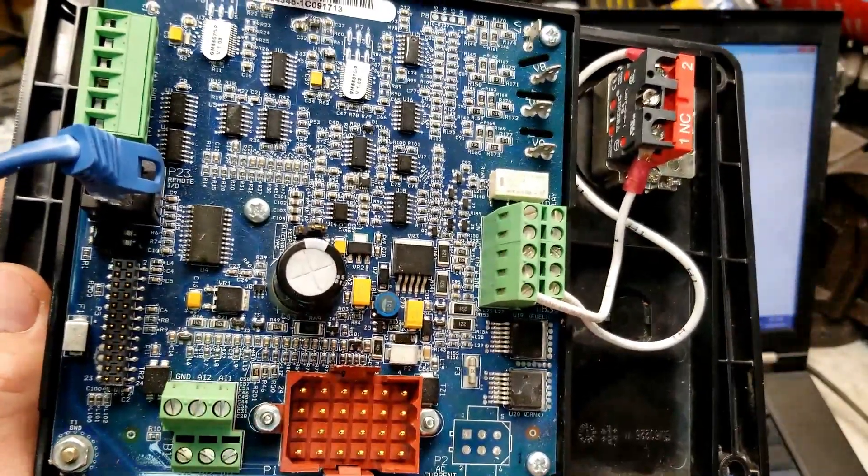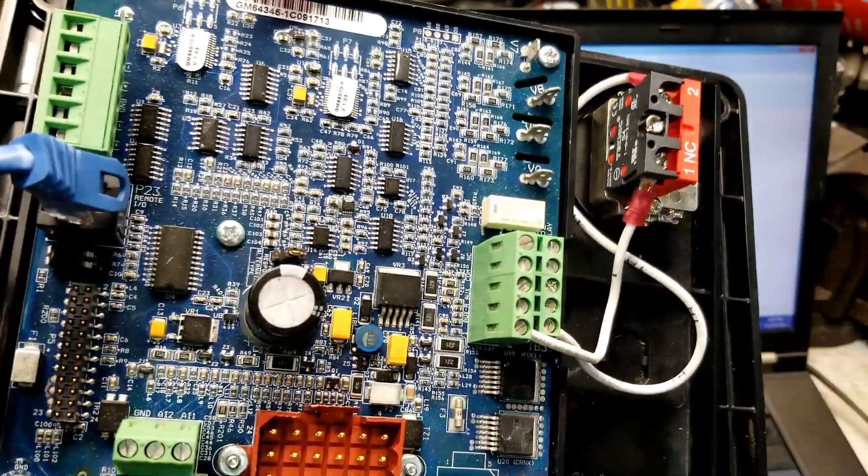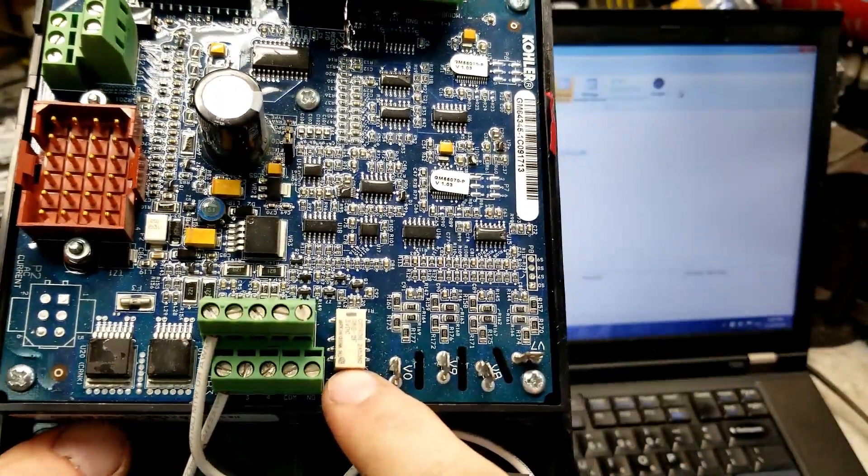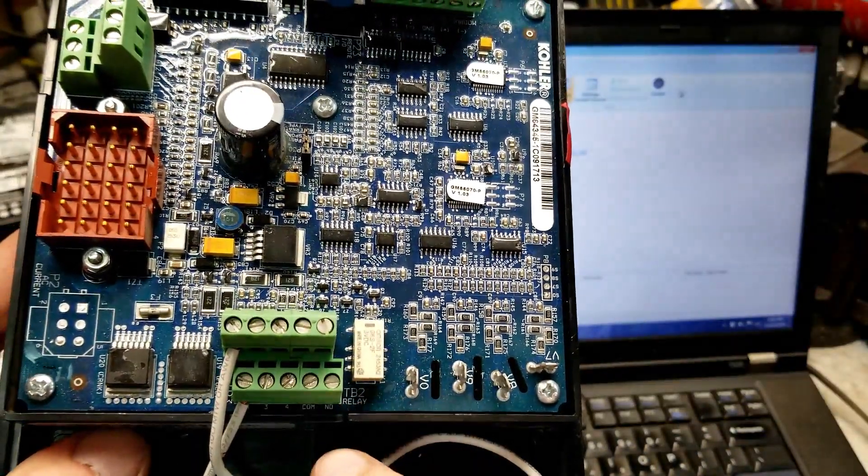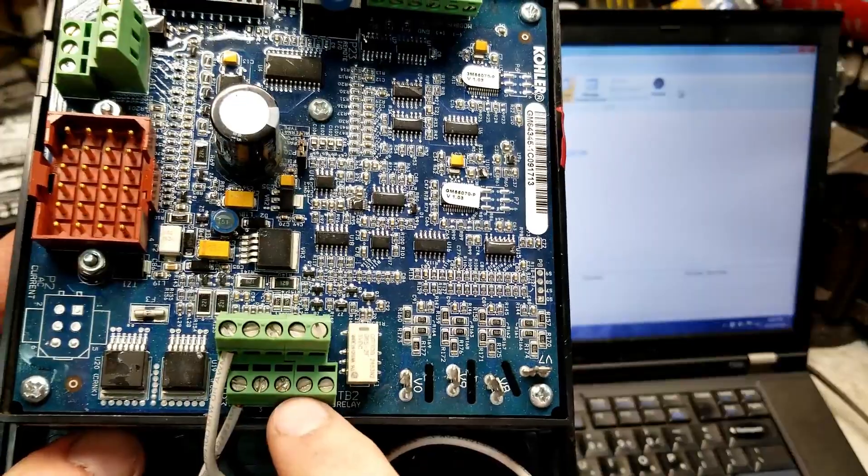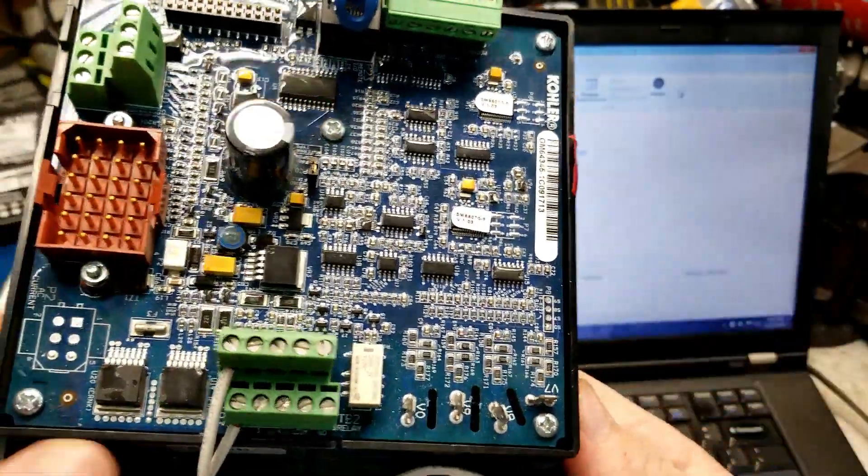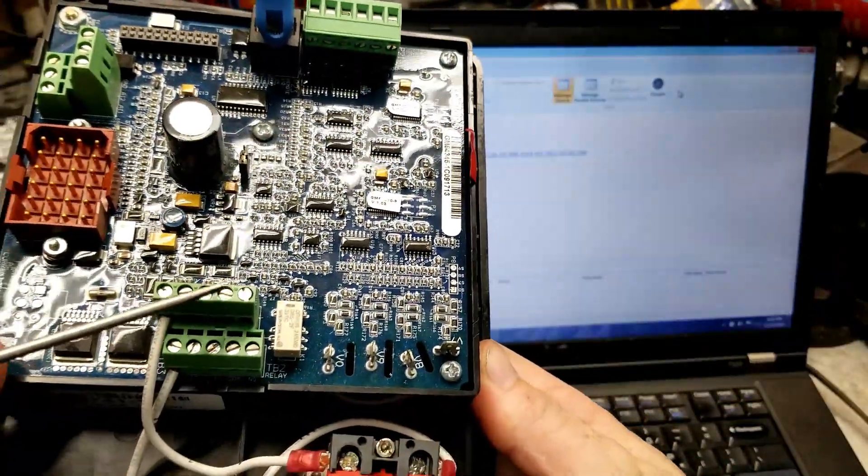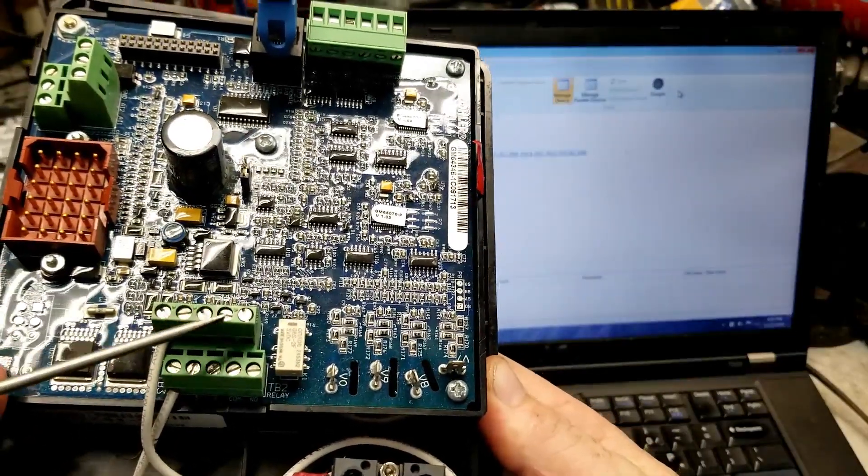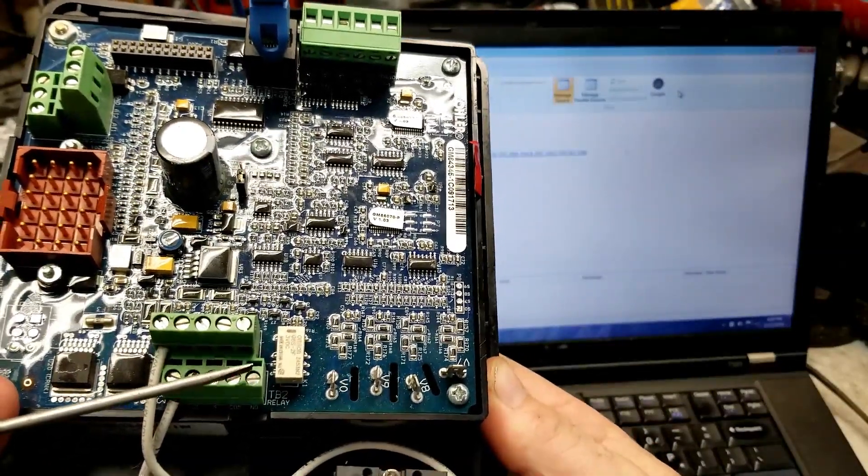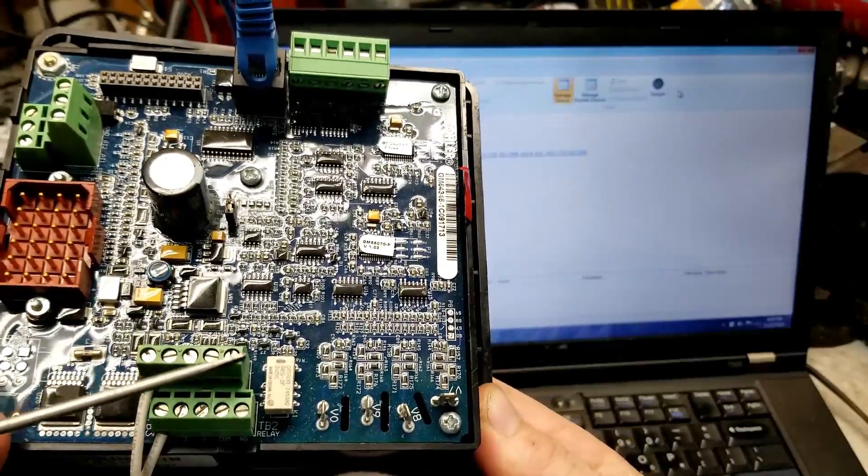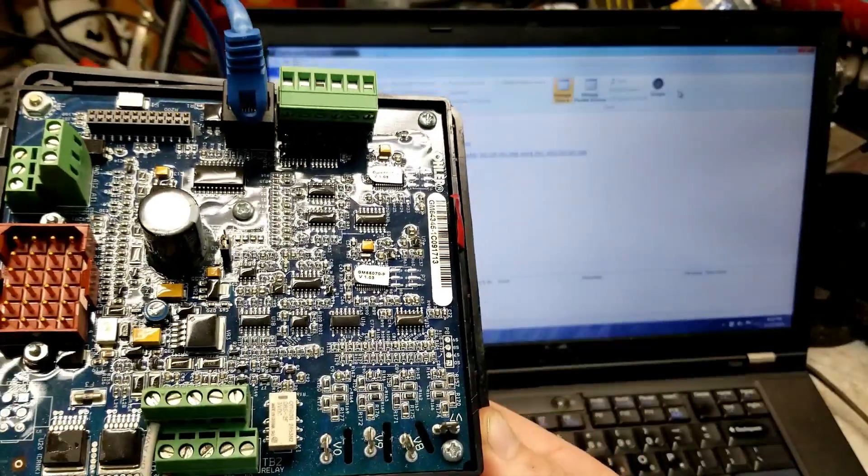And then you have two analog inputs right here for like fuel float and other whatnots. While we're here, let's talk about the one output that this has on it. It's the second wire. And let me get a pointer here. This one and this one right here are your common. They're both there and internally tied together. Then you have a normally open and a normally closed. They go back to this relay right here.